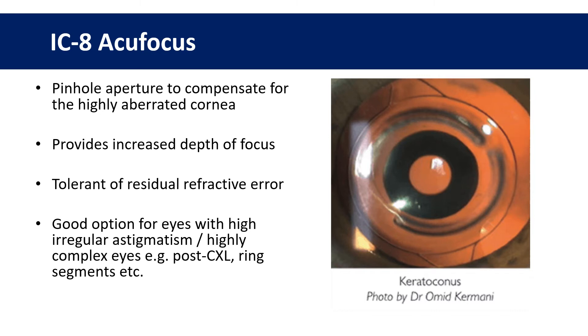In cases where you might have wanted to implant a toric lens, the IC-8 from AcuFocus is a relatively new option that may be very effective, particularly in eyes with significant irregular astigmatism. This lens consists of a pinhole aperture and is used in the same way as a simple monofocal lens. The advantage is that it compensates for the highly aberrated cornea by blocking out a lot of light coming from the periphery, increases depth of focus, and is tolerant of residual refractive error.